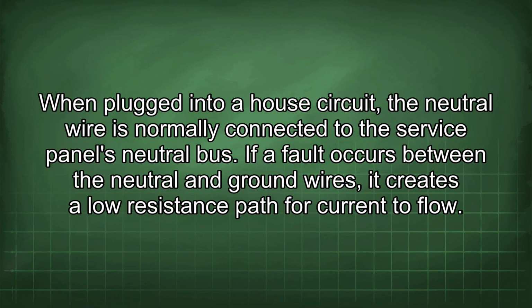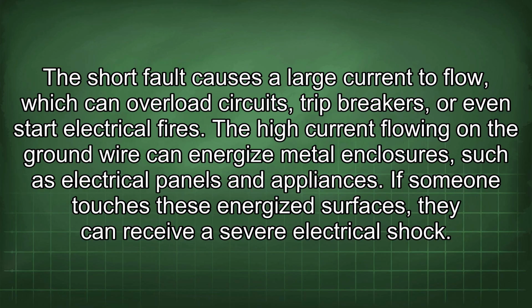When plugged into a house circuit, the neutral wire is normally connected to the service panel's neutral bus. If a fault occurs between the neutral and ground wires, it creates a low resistance path for current to flow. The short fault causes a large current to flow, which can overload circuits, trip breakers, or even start electrical fires. A high current flowing on the ground wire can energize metal enclosures, such as electrical panels and appliances. If someone touches these energized surfaces, they can receive a severe electrical shock.